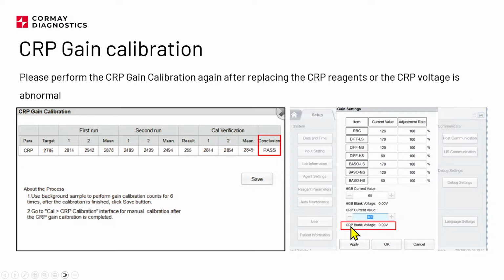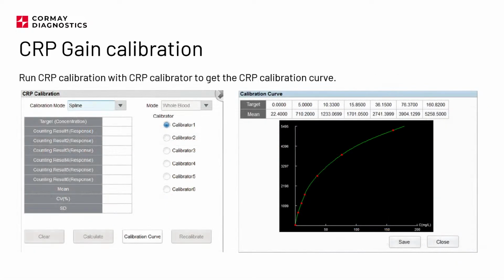What else can be a possibility for this thing? The CRP blank voltage. Maybe it's too high, maybe it's too low. So it's worth seeing what the CRP blank voltage is. The next step, if we decided to start with the CRP calibration, is to perform this calibration. As I said, this is a 6-point calibration, and this is the calibration curve. As you can see, it's not linear. It's a spline type.